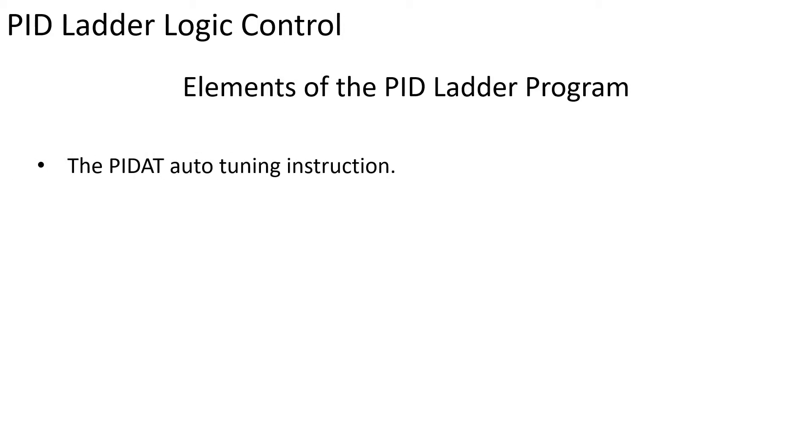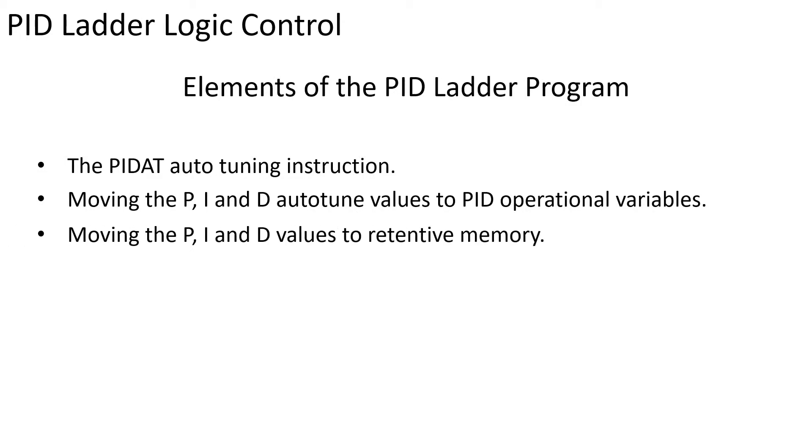The basic ladder elements of the PID control to be covered in this video are: the PID auto-tuning instruction, moving the PID auto-tune values to PID operational variables, moving the PID variable values to retentive memory, loading the PID variable values from retentive memory to operational memory on startup.